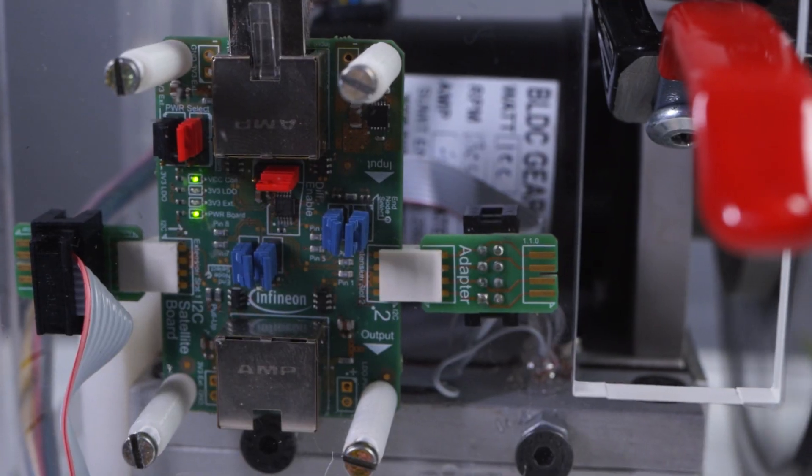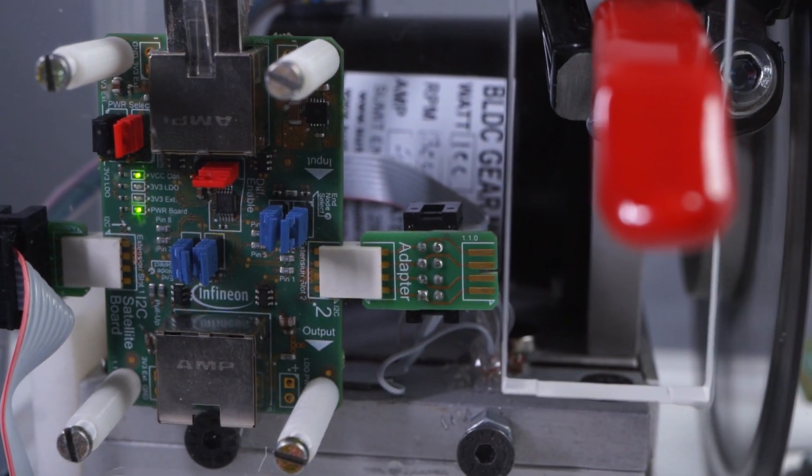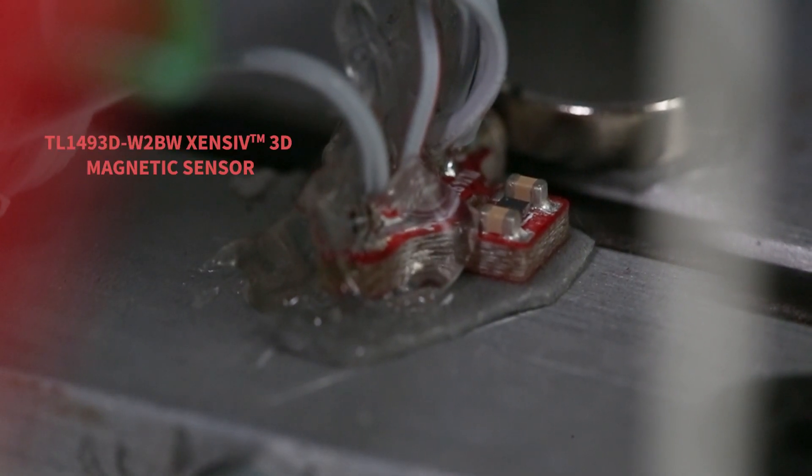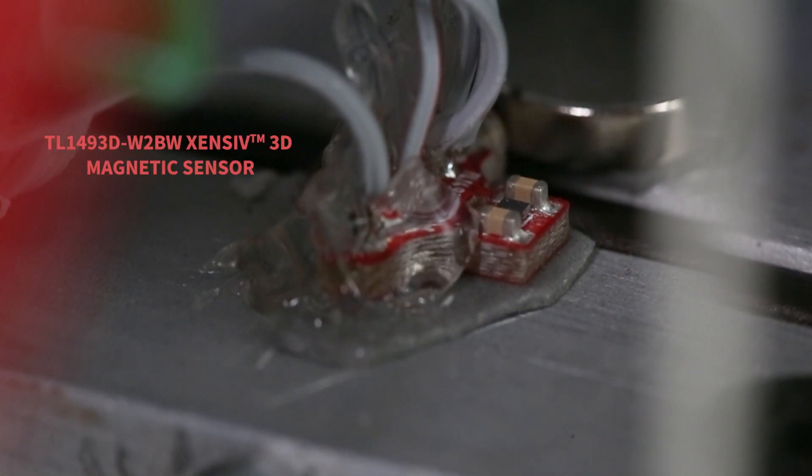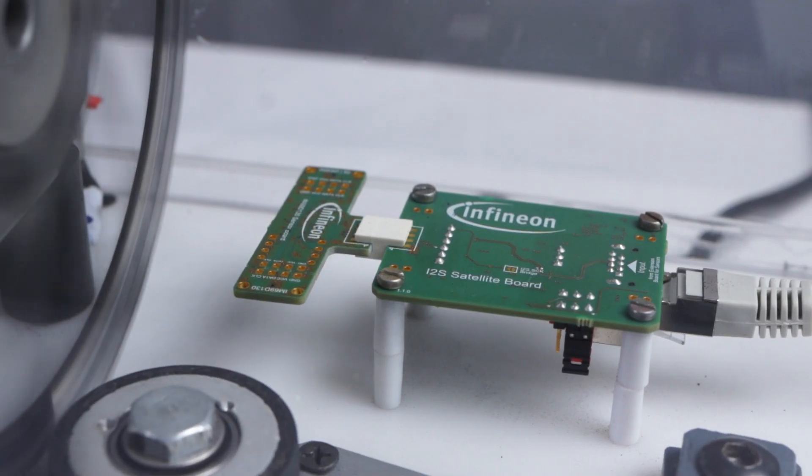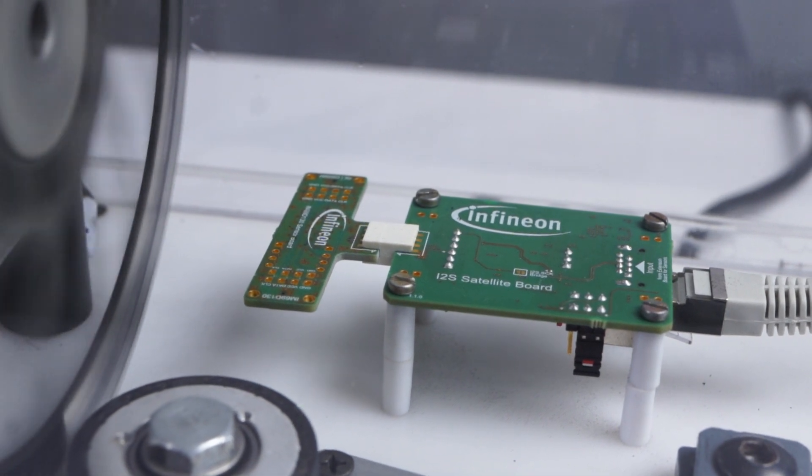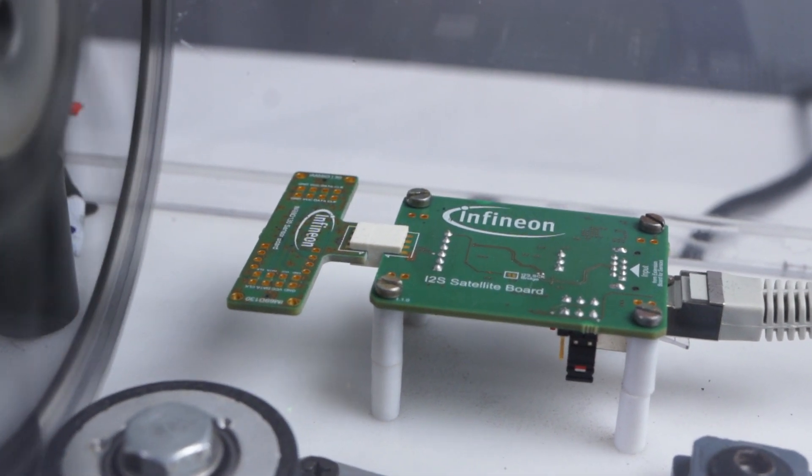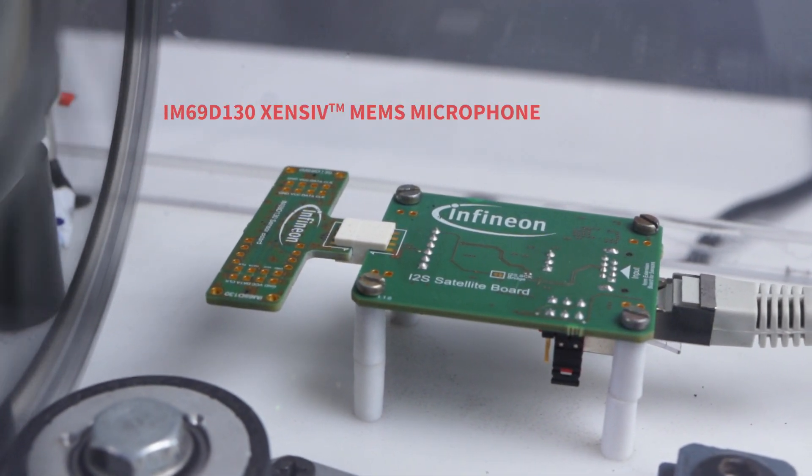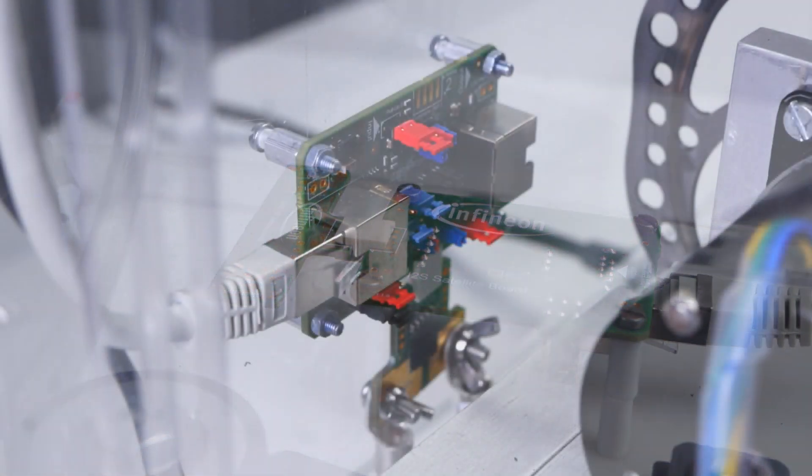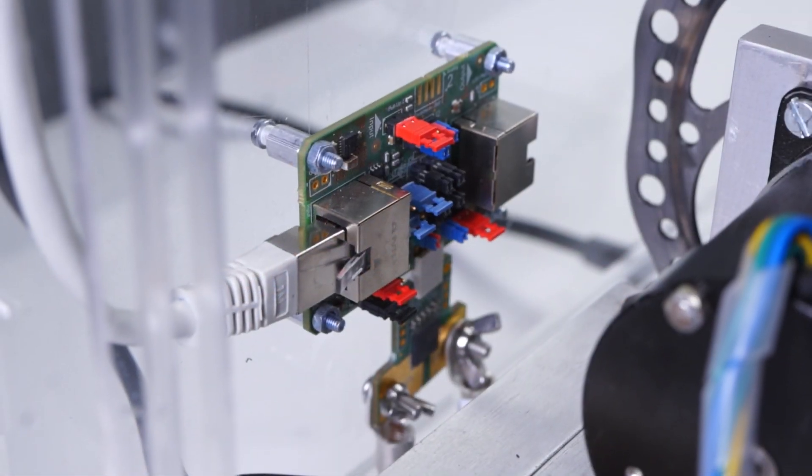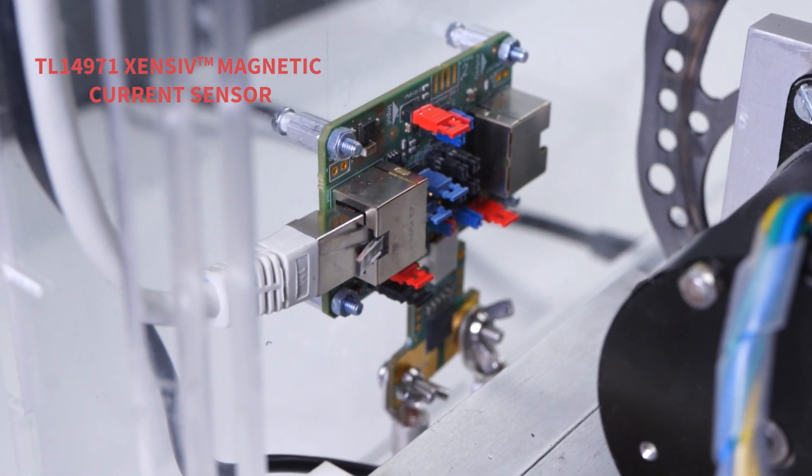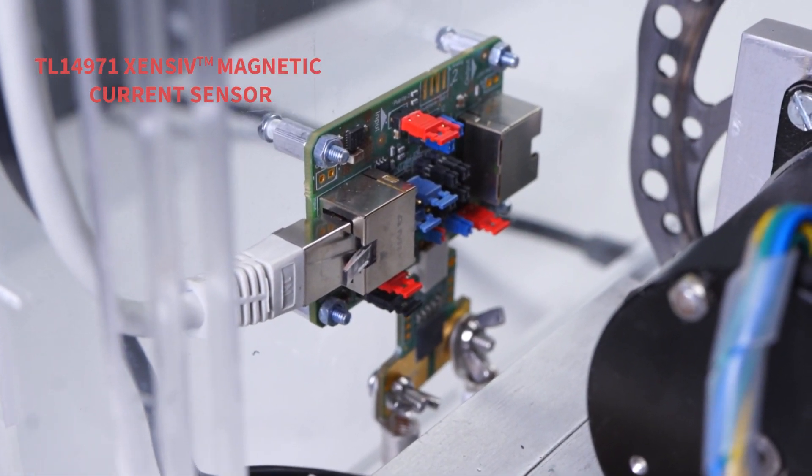The system is now actively monitoring the sensors for faults. Any abnormal vibrations or changes in mechanical position is sensed using the 3D magnetic sensor. Abnormal noise like a faulty bearing or unwanted friction is sensed using the MEMS microphone. Overload or overcurrent conditions are sensed using the hall-based current sensor.